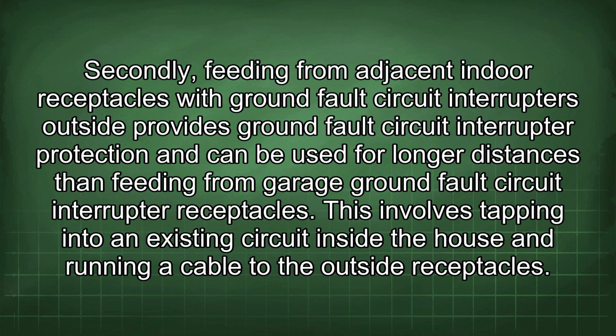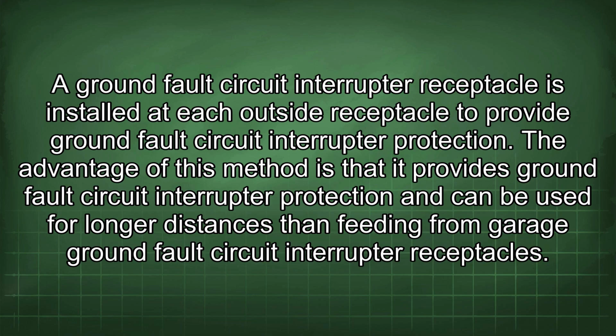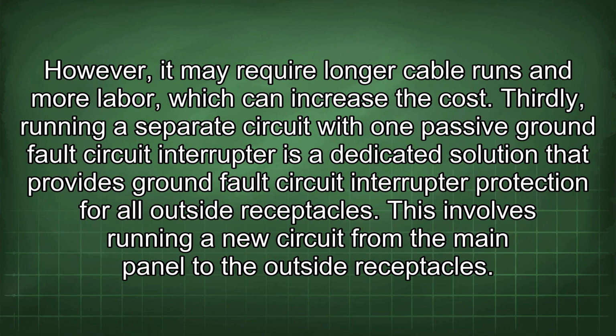Secondly, feeding from adjacent indoor receptacles with ground fault circuit interrupters outside provides ground fault circuit interrupter protection and can be used for longer distances than feeding from garage ground fault circuit interrupter receptacles. This involves tapping into an existing circuit inside the house and running a cable to the outside receptacles. A ground fault circuit interrupter receptacle is installed at each outside receptacle to provide ground fault circuit interrupter protection. The advantage of this method is that it can be used for longer distances. However, it may require longer cable runs and more labor, which can increase the cost.